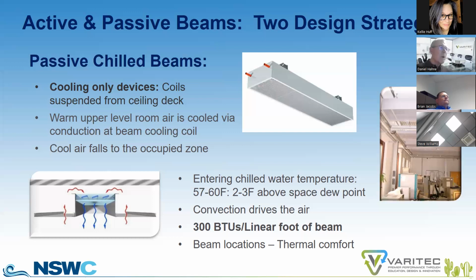You want to maximize the temperature differential at the beam so that you have more heat transfer. So the more heat transfer you have, the more efficient the system you have. Chill water is supplied to a passive beam coil loop at 2 to 3 degrees above space dew point. Controlling humidity in a building with a decoupled hydronic system for active and passive chill beam systems is a must. Chill water should be supplied at 2 to 3 degrees above space dew point.